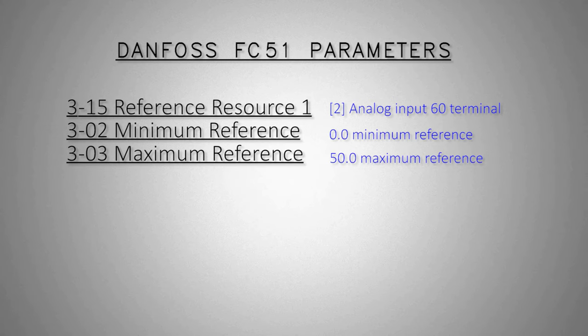There are two other parameters I want to discuss: minimum and maximum reference, parameters 3-2 and 3-3. These two parameters define the minimum speed of the motor at 4 mA and the maximum speed at 20 mA analog input signal. For this example I set 0 Hz speed at 4 mA and 50 Hz at 20 mA analog input signal.